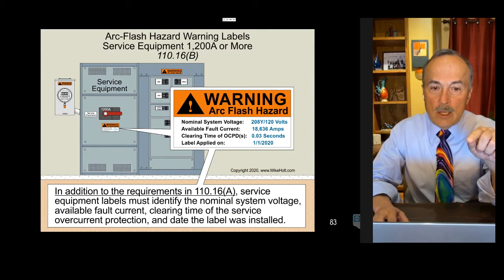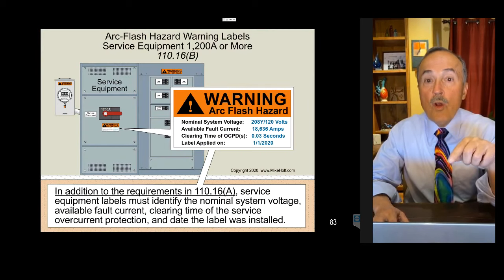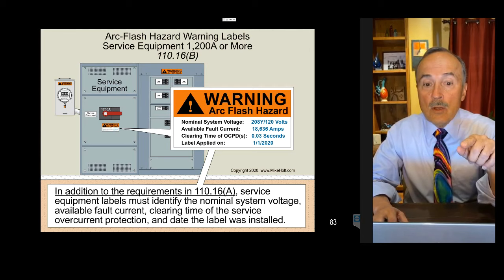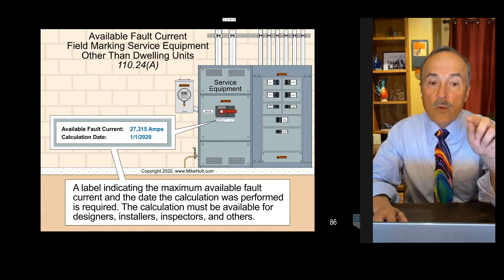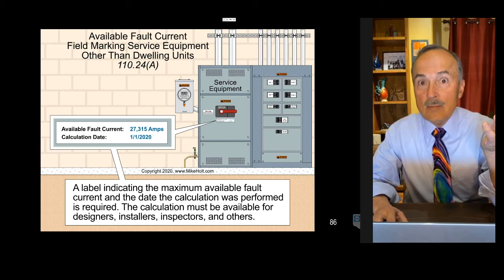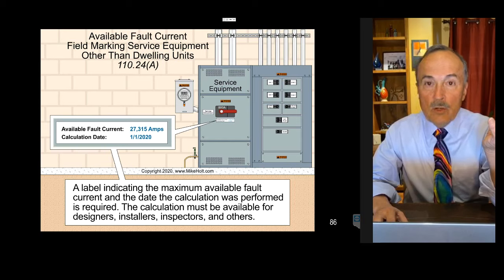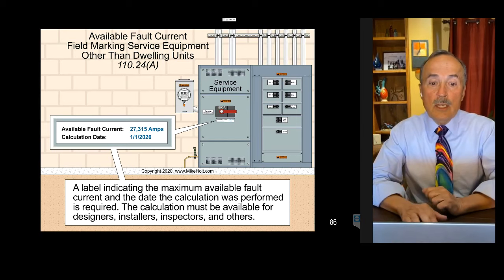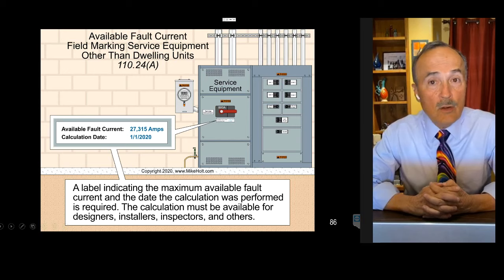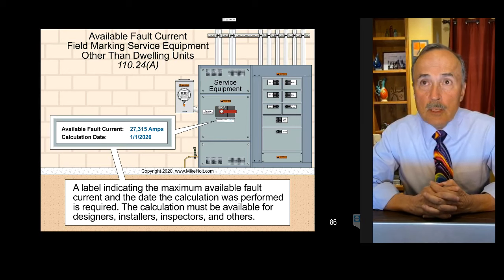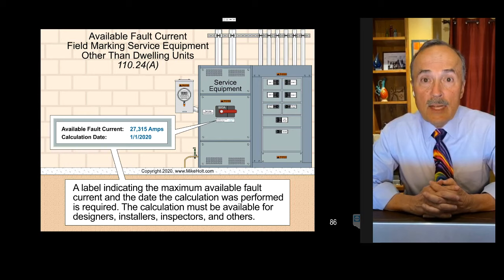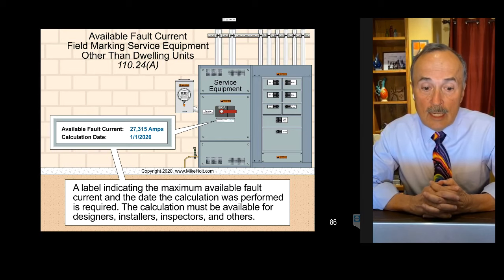And then there's another rule, 110.24(A). It says available fault current markings at service equipment other than dwelling units. 110.16(B) was talking about service equipment over 1200 amperes. 110.24(A) is talking about service equipment in general, which means it doesn't have to be over 1200 amperes.